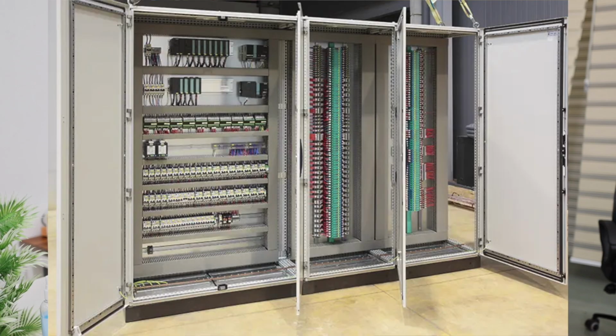So this, and the chiller temperature and the speed, the flow of water, everything depends upon the building management system. Now, before it was all a static system, but nowadays VFD, variable frequency drive systems are there, BMS systems are there, building management system. For example, the occupancy sensors are there. It depends upon the occupancy, the people.